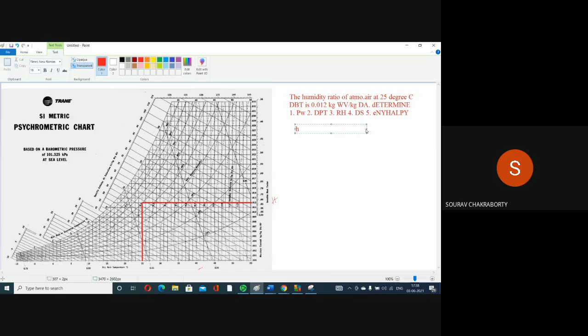So first of all, what do we need? We need the PW value. The H value is already given, 0.012. If we have the H value, we can easily calculate the value of PW, that is partial pressure of water vapor, because we know that this H, the humidity ratio or specific humidity, is 0.622 into PW divided by capital P minus PW. The H value is already given. If we put 0.012 here and capital P equal to 1.013 bar, the total pressure, then like the previous problem we can get PW equal to 0.019 bar.